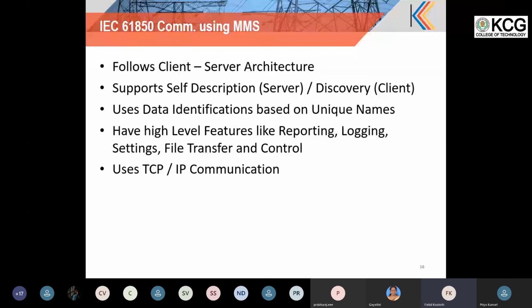Then similarly settings, that is relay setting download: I need to change certain parameters of the relay, then settings can be downloaded. Then file transfer, for example, you need to have a disturbance record file transferred from the IEDs to the station level, then that can go through the file transfer mechanism. Then there can be a control mechanism for issuing commands to operate breakers and everything, that is given from a SCADA system to the bay level equipment. This can be used. So this is on the MMS side, 61850 MMS.